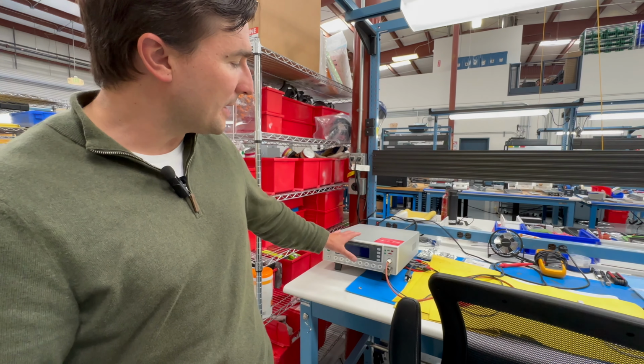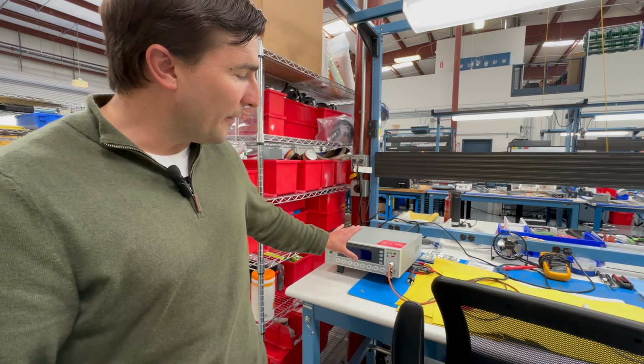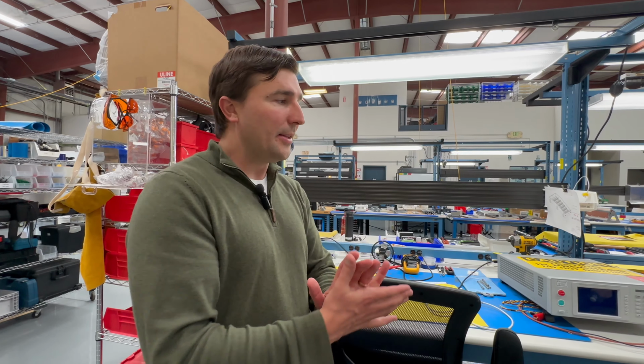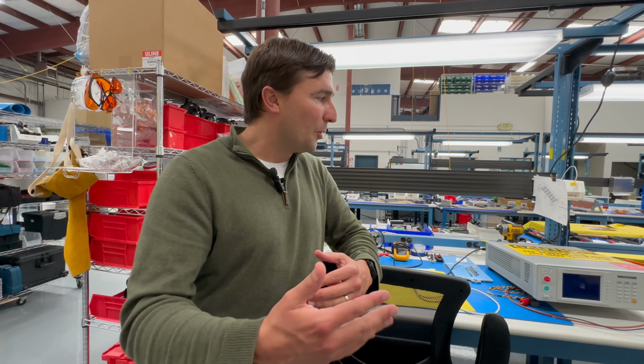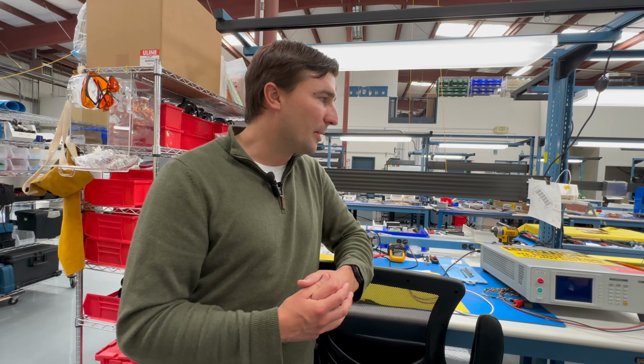So what we do is we basically, in a test, we apply 5,000 volts or up to 12,000 volts between the center of the battery pack, the electrical connections, and the outside of the battery pack, and ensure that all our electrical insulating layers are functioning as expected. And there's a huge amount of overage on that because our battery packs are typically 400 volts or 800 volts. And if we're testing at 5 kilovolts, that's about 5-6 times higher voltage than it needs to be. But you need to do that for the capability of the isolation barrier.